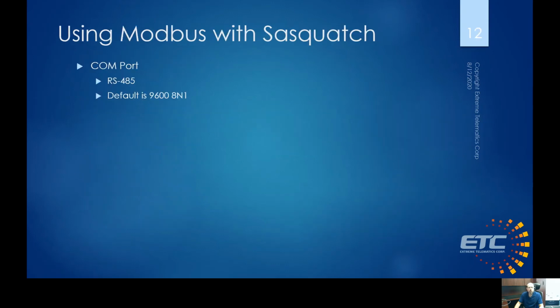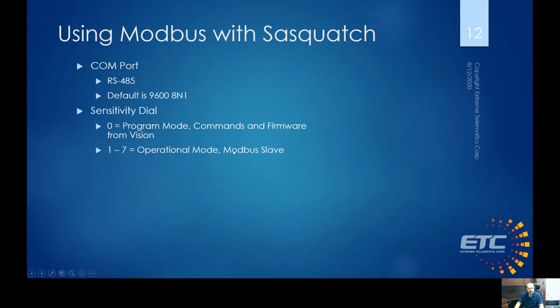All right, so when we're using the Sasquatch, we do have the Modbus port. This is used for a number of different things, such as configuration settings and retrieving the velocity value. So it is a standard RS485 connection. The COM port settings are 9600 baud, 8 data bits, no parity, 1 stop bit. This can be changed in the Modbus configuration, but this is the default you'll have to use when you first connect with it. And you can use Vision to configure it, or you can use your own Modbus tool.